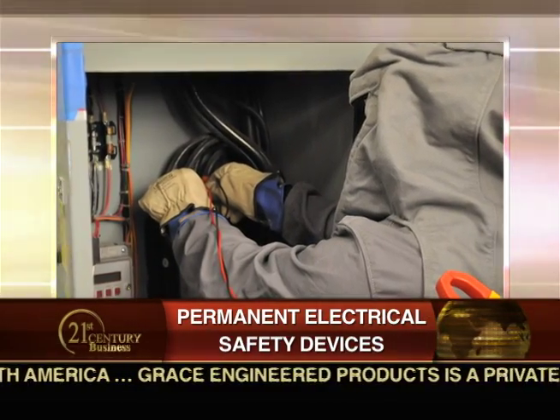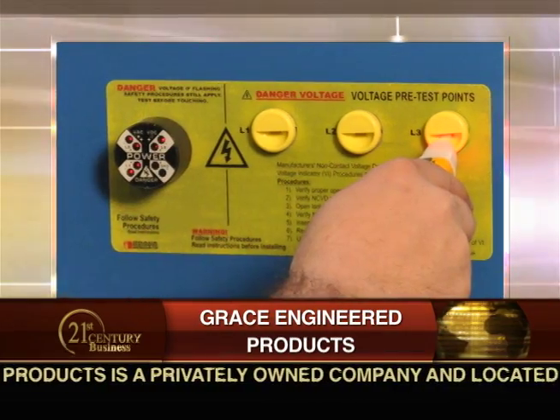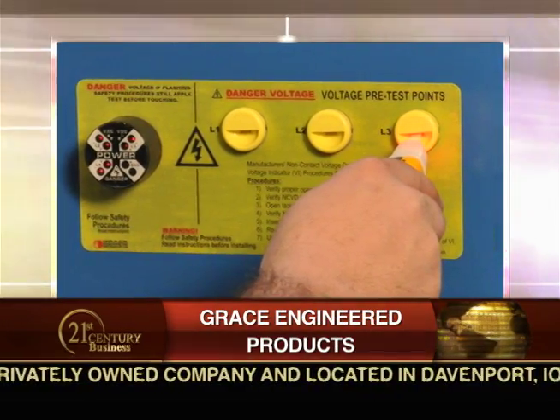So what's the main reason an arc flash would occur then? Well, interestingly, arc flashes generally occur when maintenance is being performed on electrical equipment. It can be something as simple as dropping a tool or a screw into live bus work. It can happen when you're inserting or removing a large circuit breaker from a main power distribution system.